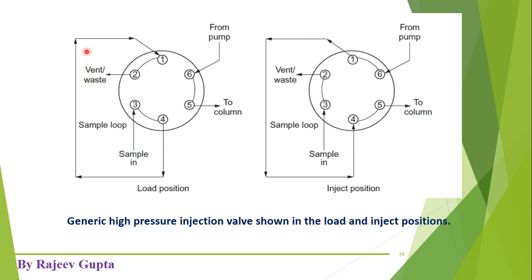So during this process the loop will also be cleaned if any impurity or other substance is already present in the loop. But of course generally before applying the loop, we clean this loop firstly, but obviously we put some higher amount of sample liquid inside this loop, so there should be no possibility of any air bubble or any impurity that could be present in our loop. So this extra amount will be wasted or vented from this point number 2.